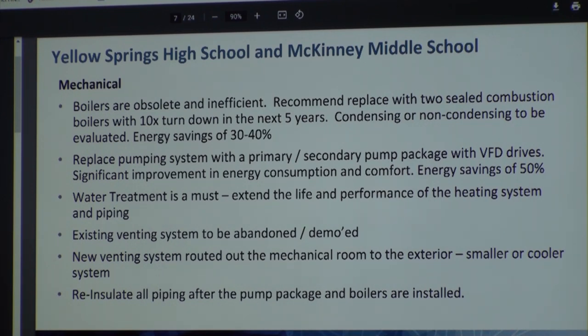So we would go back with two boilers, sized for about 65 to 75% of the maximum load, so that 90% of the time only one boiler is running. Then on a cold day, the second boiler kicks on. We'd also recommend a turn down so that on a cold morning but warm day, the boiler can run at a very low level and be very efficient.